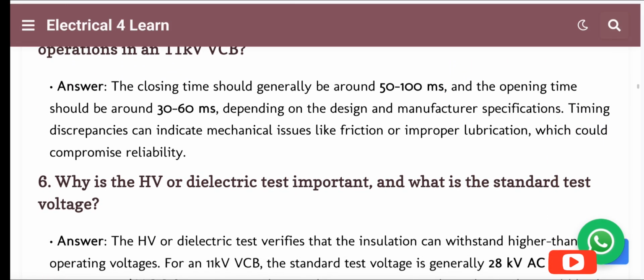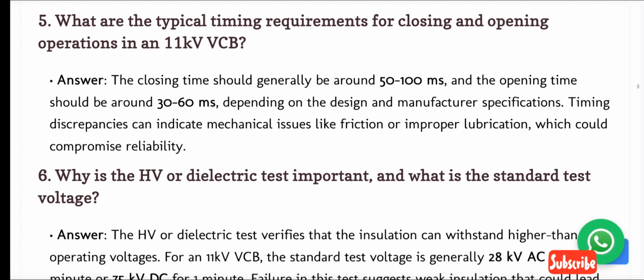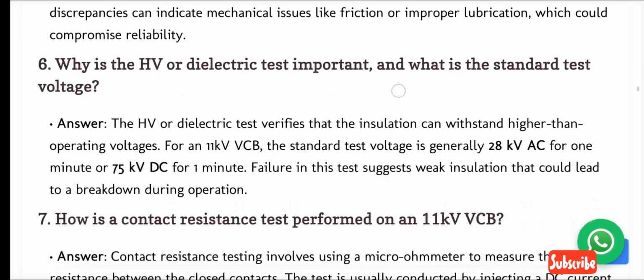5. What are the typical timing requirements for closing and opening operations in an 11 kV VCB? Answer. The closing time should generally be around 50 to 100 ms, and the opening time should be around 30 to 60 ms, depending on the design and manufacturer specifications. Timing discrepancies can indicate mechanical issues like friction or improper lubrication, which could compromise reliability.